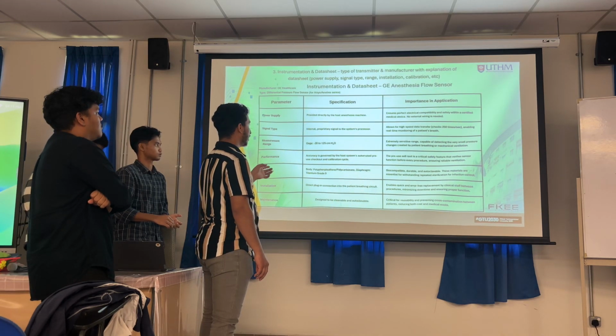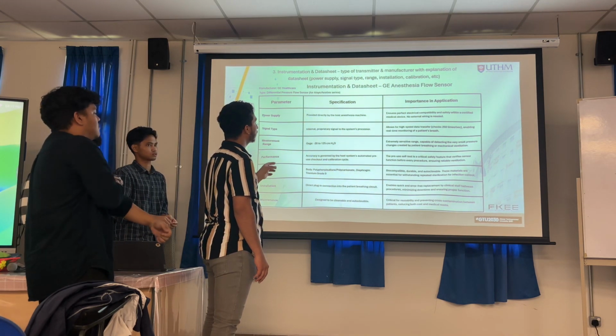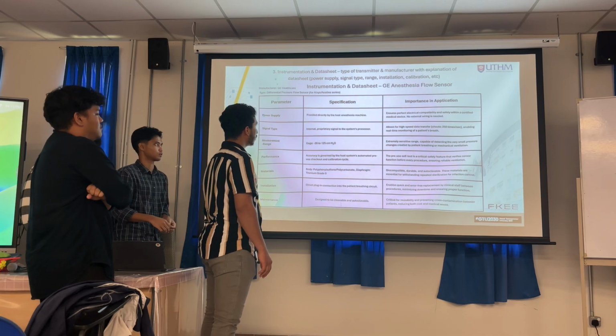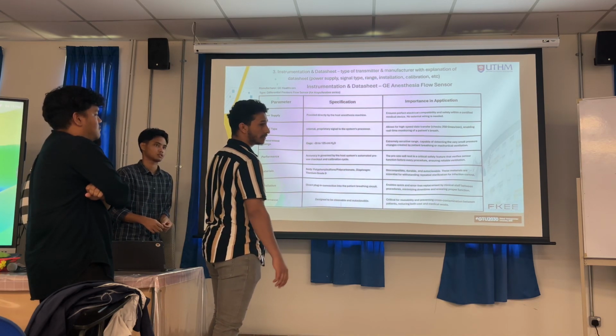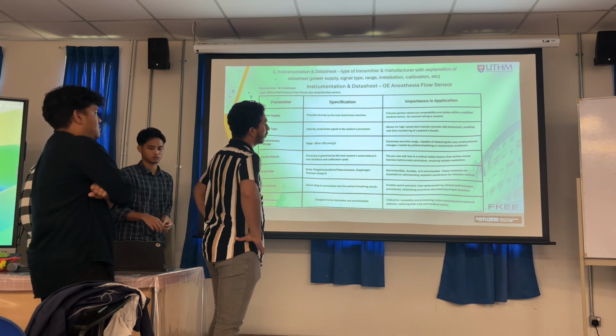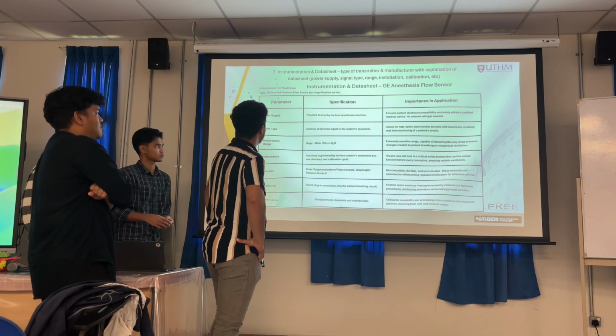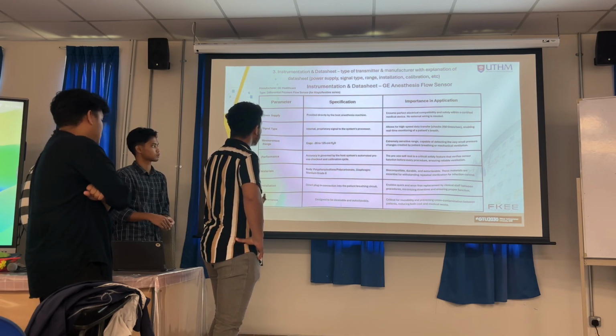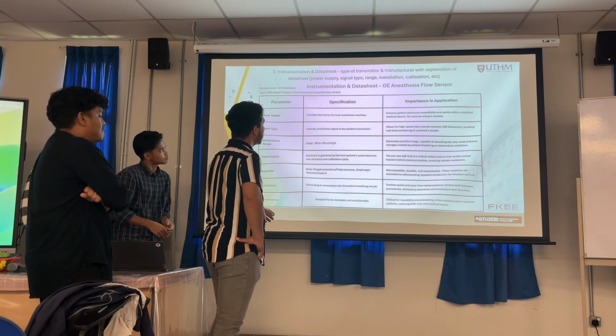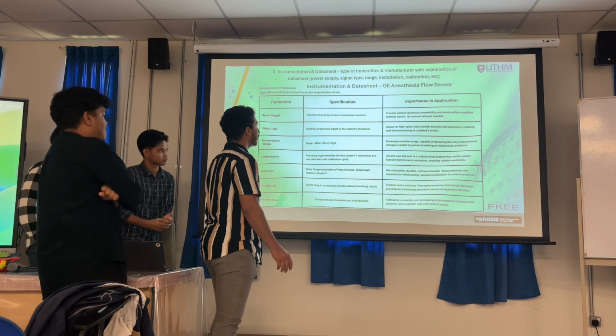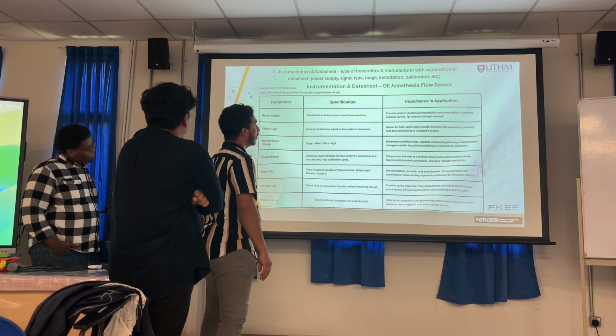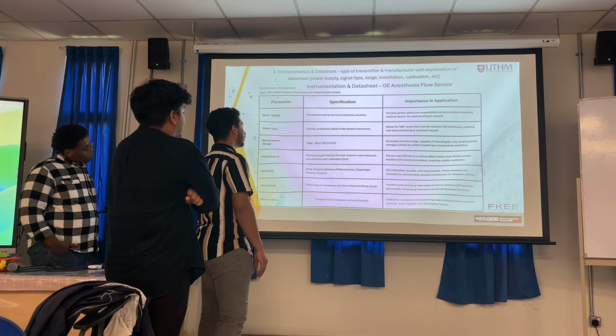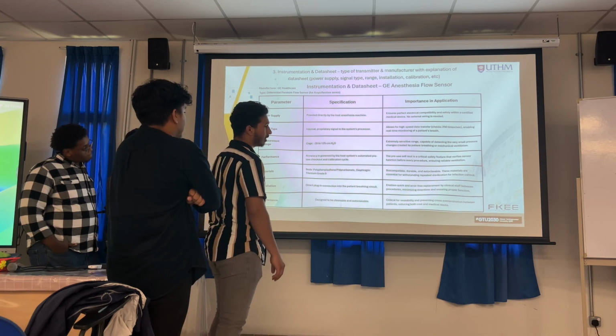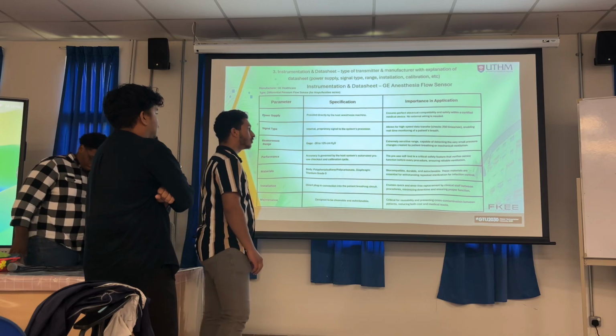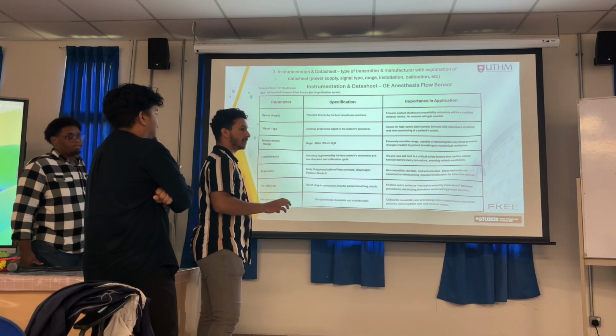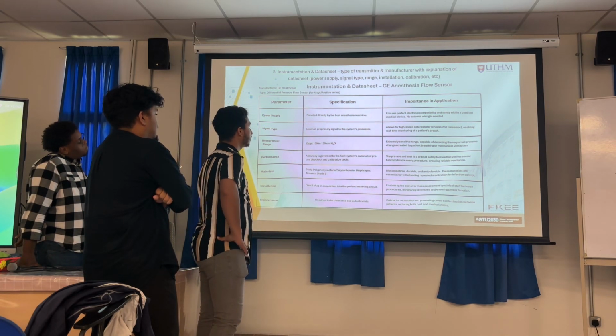Measurements: here is the gauge, it's 2 to 125 centimeters H2O. Here is the performance: accuracy is governed by the host system's automated per-use checkout and calibration cycle, which is automatically calibrated by the machine installation.